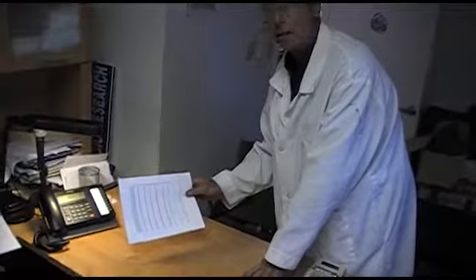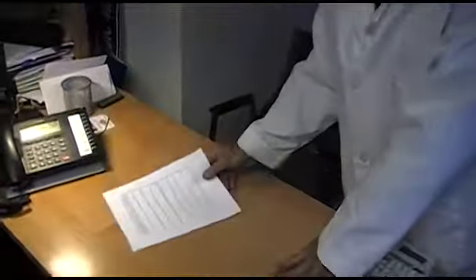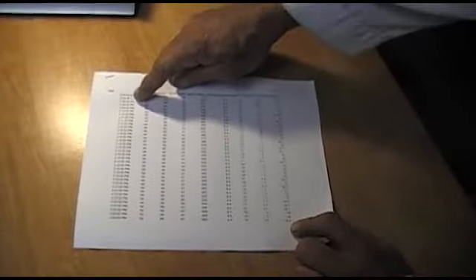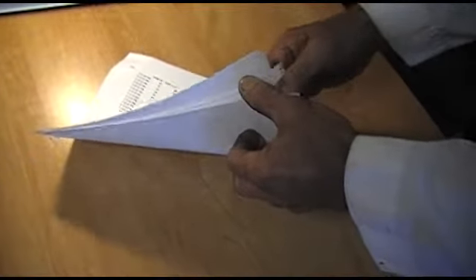We have a printout here of the information collected on the data monitoring function of the touchscreen monitor. This information is printed out in a text format that can be brought into any spreadsheet program and formatted. It provides all the information: time and date, temperature of the water in, temperature of the water out, the vessel temperature, all of this data. You can do calculative functions, such as volts times amps to get the DC watts for the electrodes, and it gives you all this information in a usable format that can then be stored, manipulated, or plotted as a graph from any spreadsheet program.